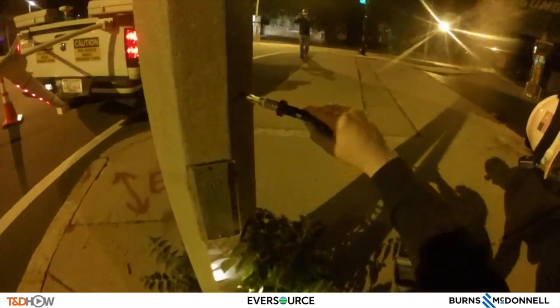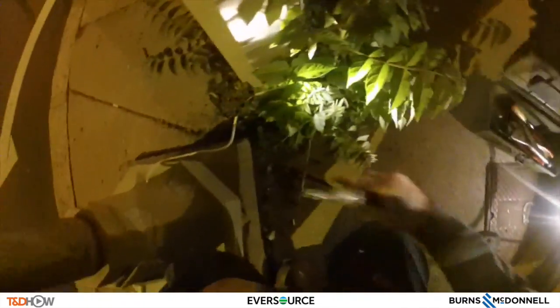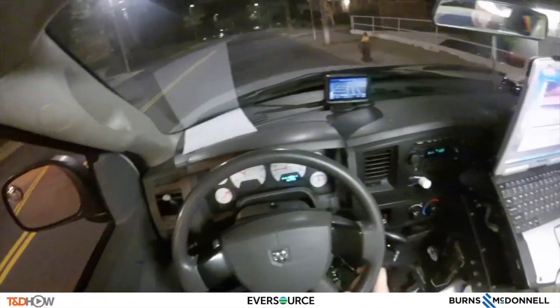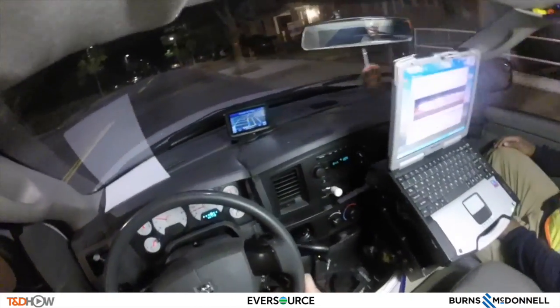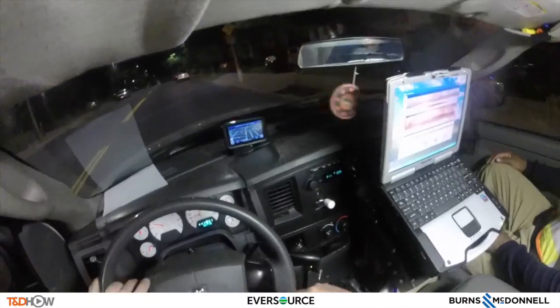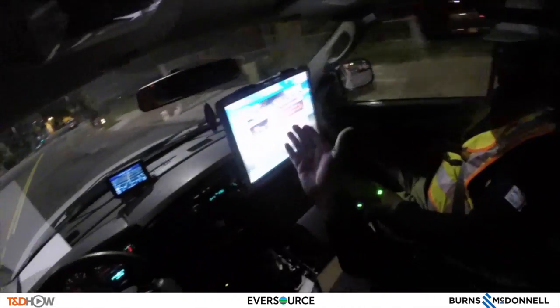Now he'll close that streetlight post back up, test once more for stray voltage, and let's go back to the truck and listen to Brian. Again, Jim, that was actually an easy one to troubleshoot because we were able to pull the neutral up. Sometimes you have to actually test it. But like you said, Jim, you see the big spike is where we just were, so now we're driving past streetlights normally, and there's no spikes at all like that.